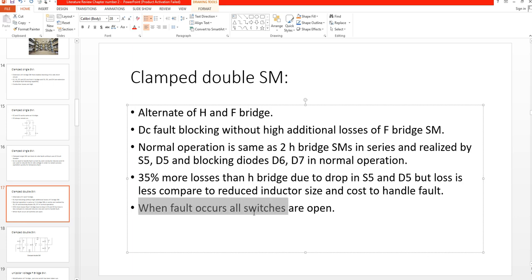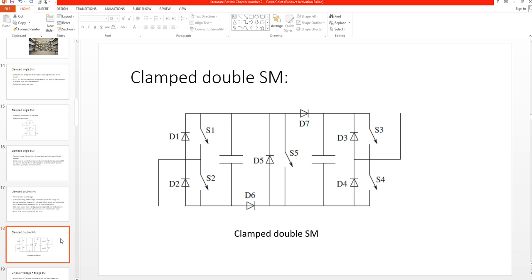Whenever a fault occurs, all the switches are open. Similar to the clamped single submodule, we consider the arm current flowing either into or out of the submodule — positive or negative respectively. When the arm current is positive, diodes D1, D4, D6, and D7 are conducting.